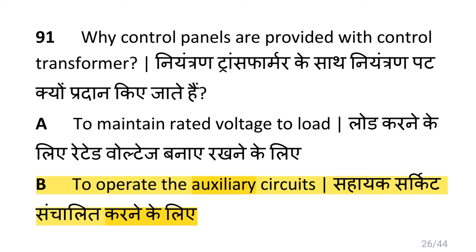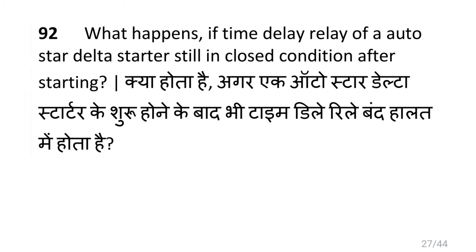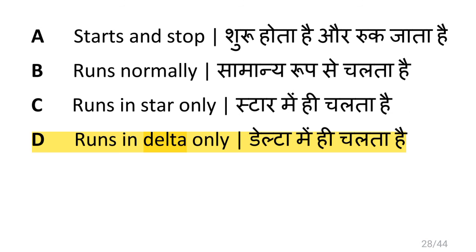Why are control panels provided with a control transformer? i.e. to operate the auxiliary circuit. What happens if the time delay relay of an auto star delta starter stays in closed condition after starting? It runs in delta only.